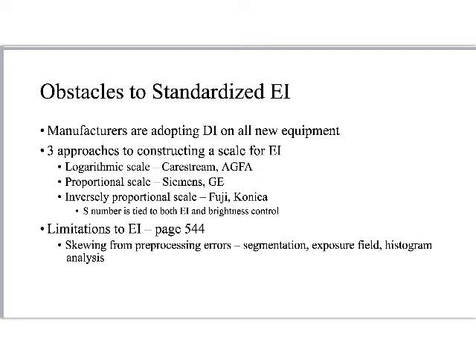I'll focus mostly on the inversely proportional scale, primarily used at most Baptist facilities — the Fuji system. In the Fuji system, the S number: if the S number is high, the exposure is too low; if the S number is low, the exposure was too high. We want to be somewhere in the middle range, normally around 200 to 400 for an S number. What I consistently see walking into facilities are S numbers that are too low.